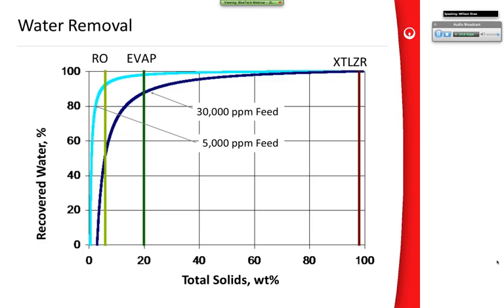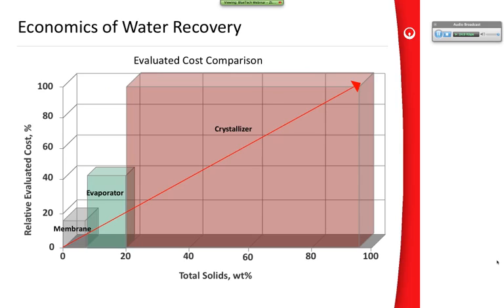This will give you an idea. I'm not going to spend a lot of time on this, but as the previous presenters have shown, RO has an upper limit as to how high you can concentrate, generally about 4 to 6%. Evaporators, maybe you can get up to 20%, and crystallizers we can get nearly to dryness. Notice that most of the water removal is done in the RO and evaporator steps, and the crystallizer does fairly minimal water recovery - but that's not its purpose. Its purpose is to get us to dryness.